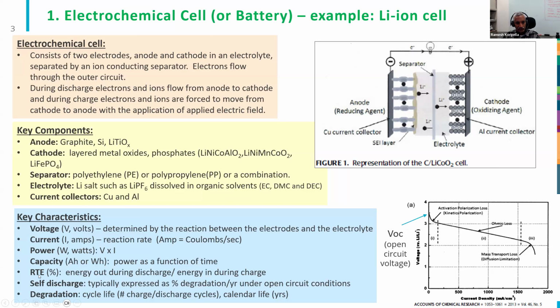You want to have a high round trip efficiency, and low self-discharge. Degradation is about cycle life - how many cycles you can operate this battery - and calendar life, how long it lasts. A typical lithium-ion battery is good for about 3,000 cycles. Some technologies last very long cycles, but some are not as good. Calendar life for lithium-ion batteries is typically 10 to 15 years.